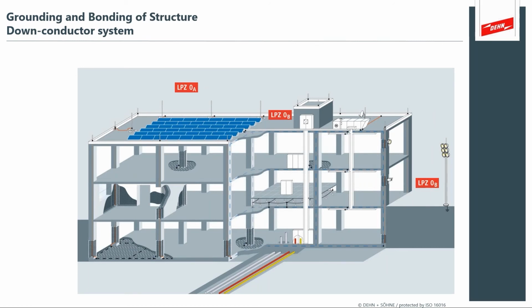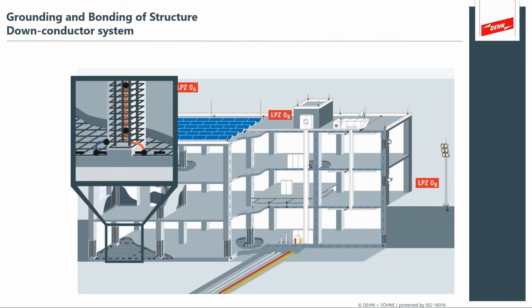So here we have a nice illustration showing that earthing system, and it's the down conductor system married and bonded to the foundation earth electrode. And this allows you to have accessible points to install additional earthing and bonding around your equipment. So here we see these yellow pads would be bonding points within and married to the cement columns and the rebar systems. So in a system like this, you could use the buried down conductor that's immersed in this concrete as your down conductor system, and it's bonded with the structure.